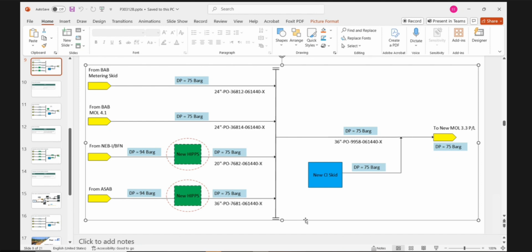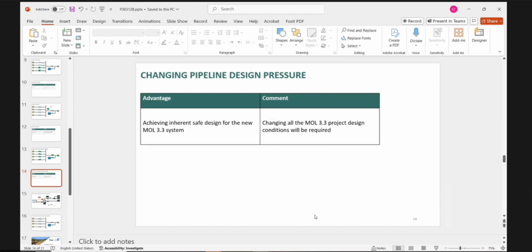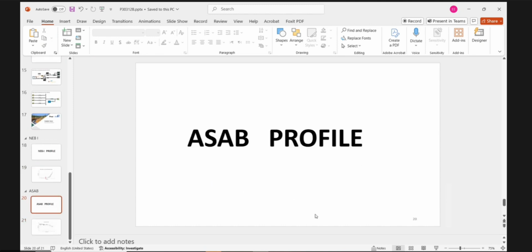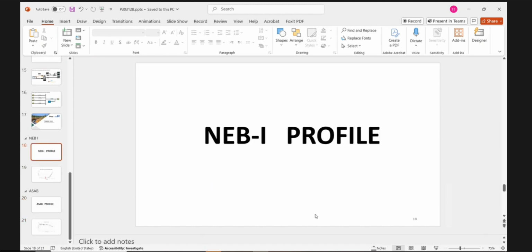Not necessarily. We can, as long as the complete function, if we can ensure it meets SIL 3. Yes, okay, this is okay. We have many applications where for the logic solver we use a SIL 3 PLC. It will not be a separate dedicated one. So we have switched to the ABB 800xA HMI controller, which is SIL 3 anyway.